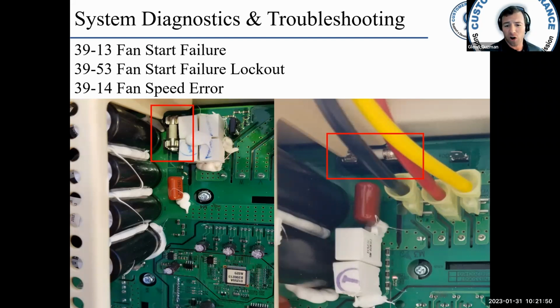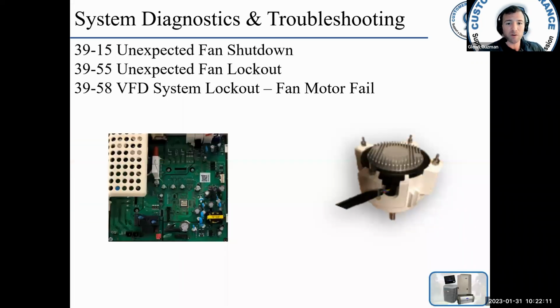You can also look at the RPM on the UI and the app, but you wouldn't really know what the requested RPM is versus the feedback. If the motor seems to be okay, ohm the motor, and you could have a VFD that is not reading the feedback signal correctly. You may need to troubleshoot the VFD in that case as well.